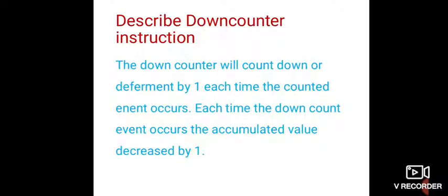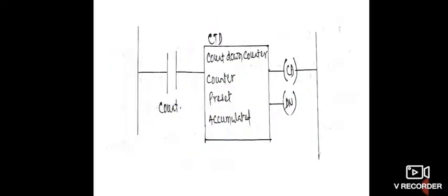The down counter instruction is similar to the up counter, but it acts in reverse order. Whenever the input transitions from low to high, the counter decrements by 1 and continues counting down until it reaches 0. When the counter becomes 0, we can trigger the output activity — for example, to close a door. The ladder diagram for the down counter is shown in the figure.